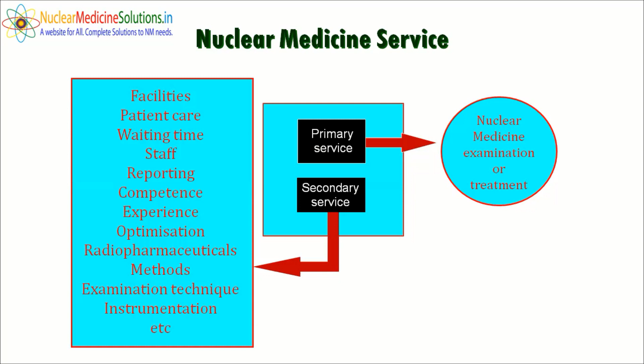So the objective of quality assurance is to improve the quality of the diagnostic information, use a minimum amount of radionuclide activity to get the desired diagnostic information, and make effective use of available resources. First we do an acceptance test or reference test when we receive any nuclear medicine equipment in the department. In this acceptance test, we perform certain tests and match our values with the manufacturer's values, and these values become our reference values. Then we do routine quality control tests to check the performance of the nuclear medicine equipment, a gamma camera or a SPECT, on a daily, weekly, monthly, quarterly and yearly basis.